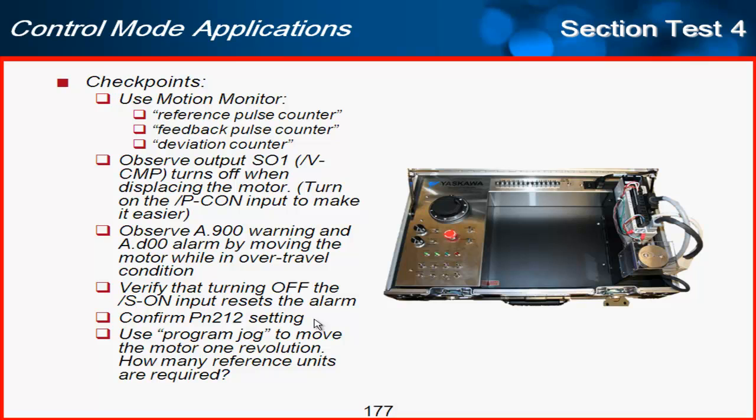And then finally, let's use program jog to move the motor one revolution. How many reference units are required? The answer to that would be 36,000. So I get 360 degrees out of my 0.01 reference unit.